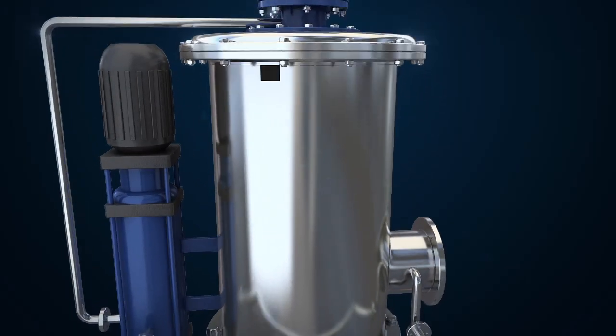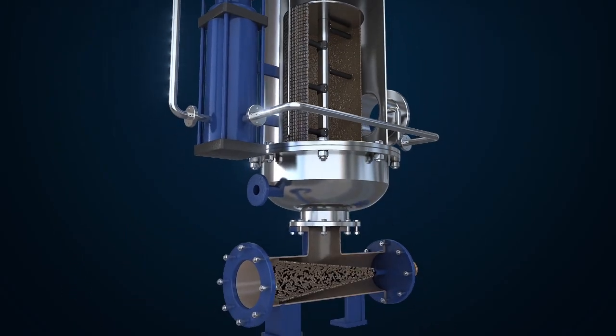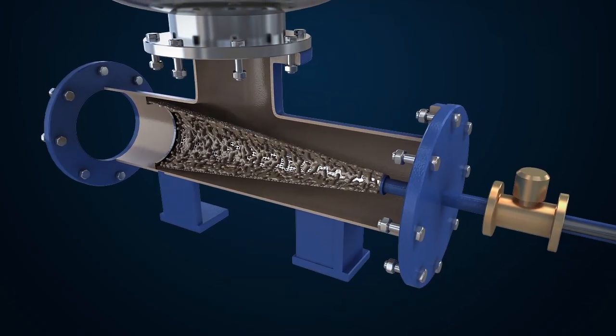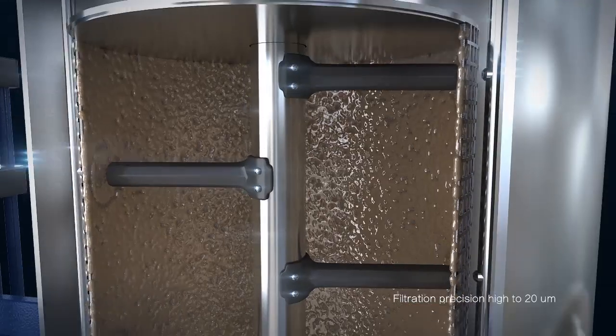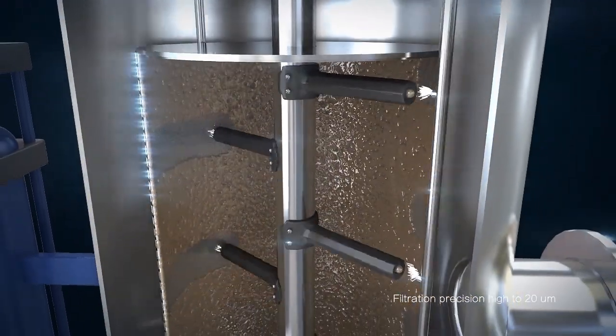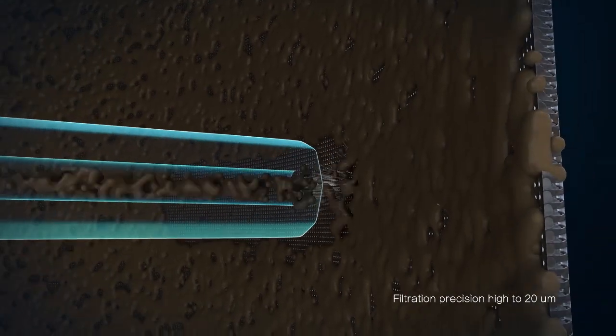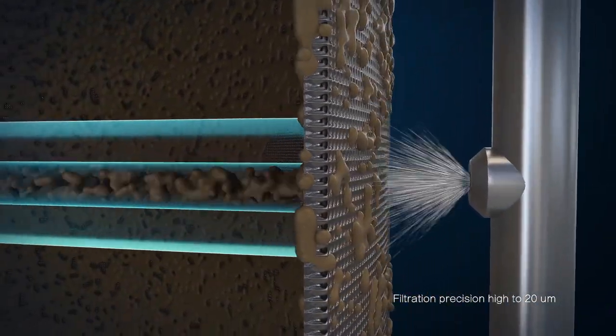For the filter, when the differential pressure reaches set value, system will back flush automatically and use 20 bar high pressed water to flush the filter, so which can run efficiently in any water condition.